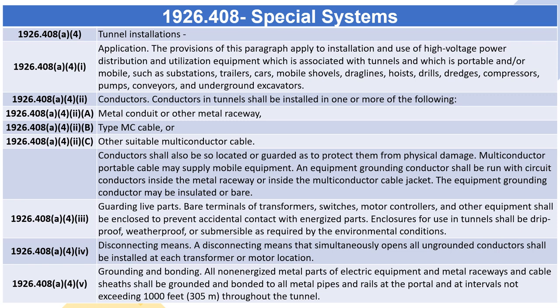1926.408(A)(4)(iv) — Disconnecting Means. A disconnecting means that simultaneously opens all ungrounded conductors shall be installed at each transformer or motor location. 1926.408(A)(4)(v) — Grounding and Bonding. All non-energized metal parts of electric equipment and metal raceways and cable sheaths shall be grounded and bonded to all metal pipes and rails at the portal and at intervals not exceeding 1,000 feet (305 meters) throughout the tunnel.